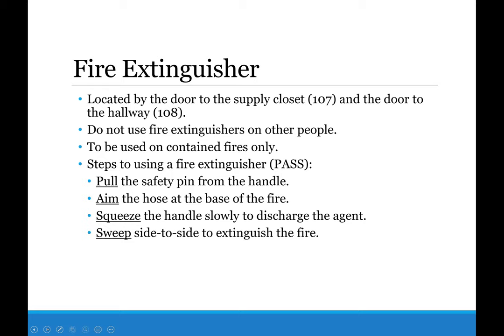We have two fire extinguishers, located in classrooms 107 and 108. We never use fire extinguishers on another person — we use fire blankets only on humans. Fire extinguishers are to be used on contained fires only; if it's a large fire, we evacuate. The steps to using a fire extinguisher are PASS: Pull the safety pin from the handle, Aim the hose at the base of the fire — never the top, Squeeze the handle slowly and discharge the agent, and Sweep from side to side to extinguish the fire.